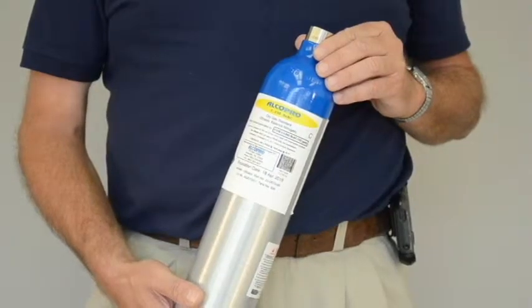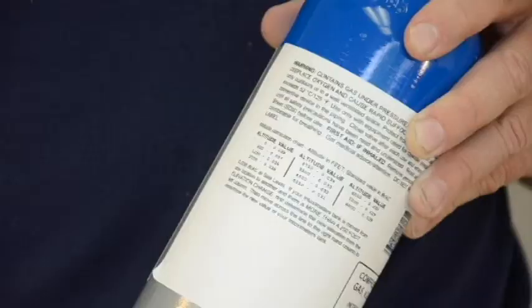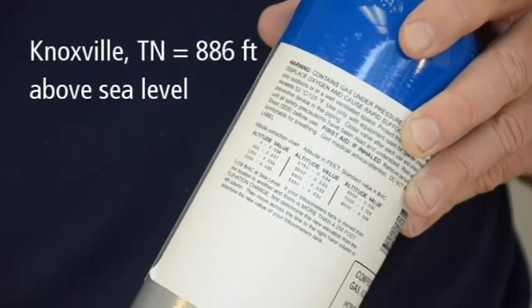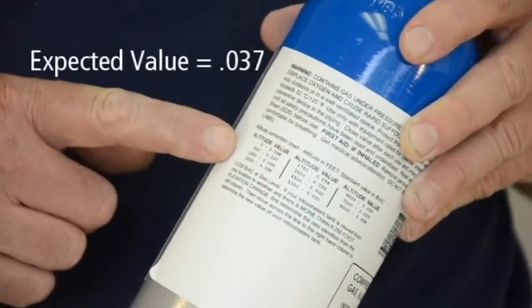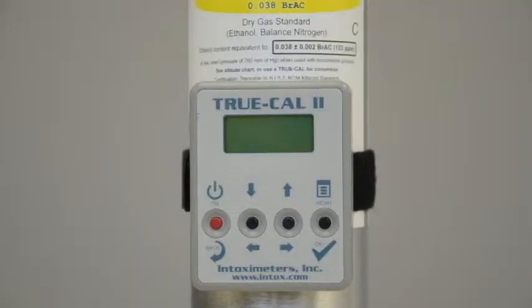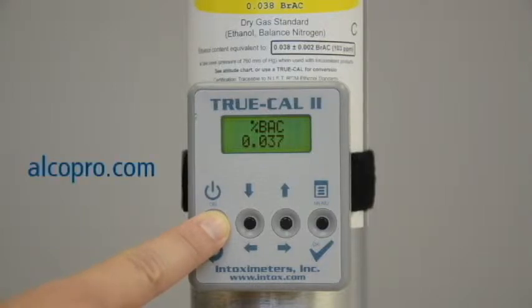The expected or target value of your gas standard can be derived by referencing the altitude chart on the back of your tank. For example, if you are performing an accuracy check in Knoxville, Tennessee, which has an altitude of 886 feet above sea level, the altitude chart shows the expected value of the alcohol gas tank to be .037. You can also derive the expected value by using a TruCal device, which uses atmospheric pressure to predict the expected value of the gas. You can purchase a TruCal device at alcopro.com.